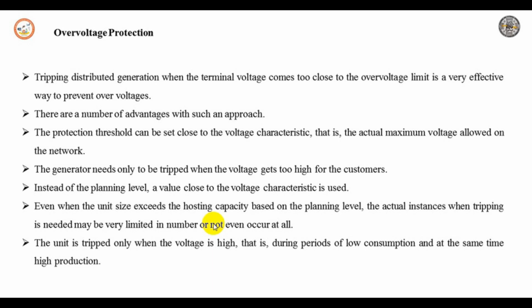The unit is tripped only when the voltage is high. This is during the period of low consumption and at the same time high production. The amount of energy produced by the unit is not influenced by the estimations on maximum voltage drop or maximum production. So this is obviously a huge gain compared to setting a maximum production limit, which is based on the worst case scenario. The method is very easy to implement, with none or very limited extra investment needed. What is needed is the voltage measurement, a simple relay and a breaker.